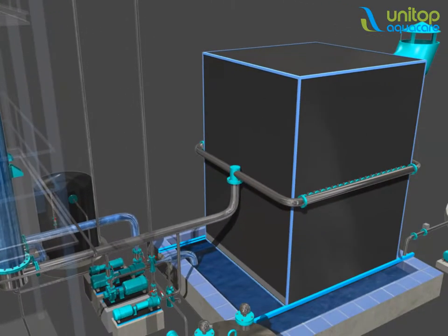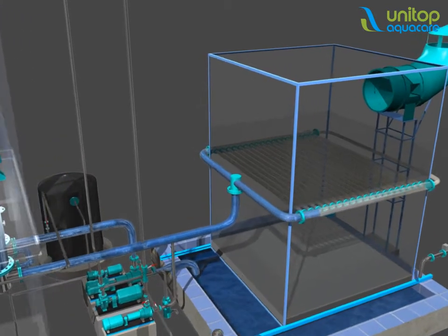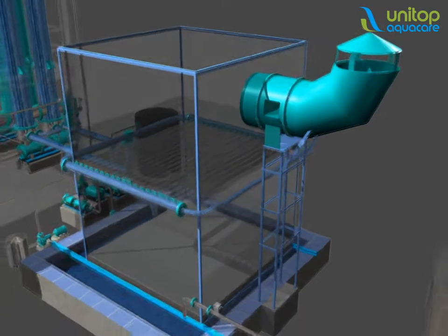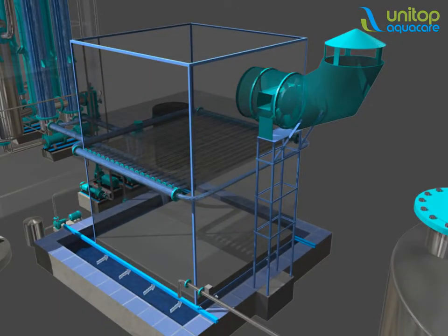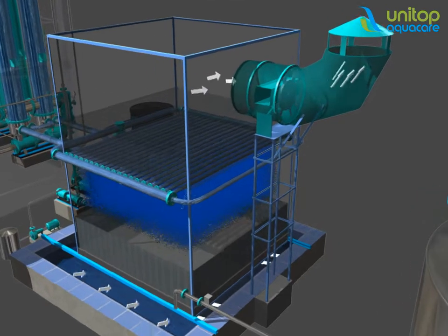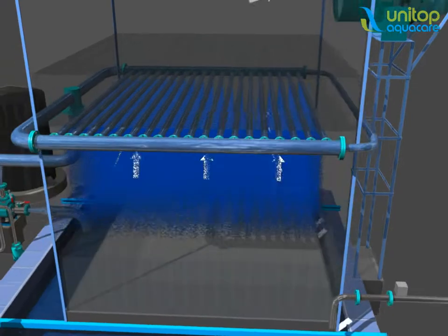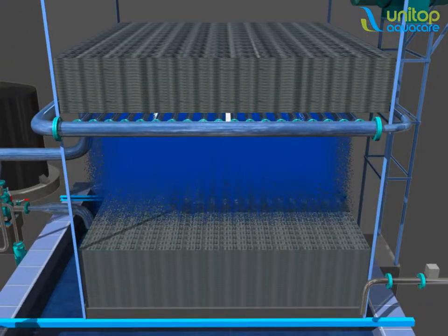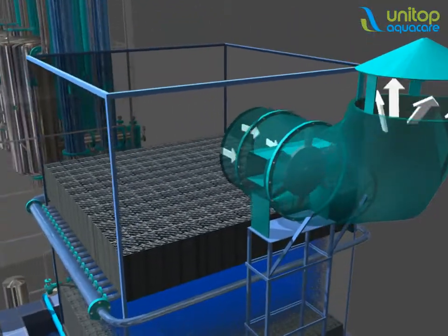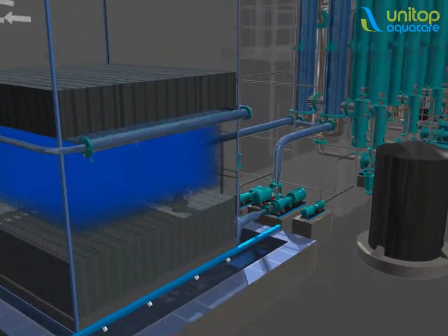During the process, the sensible heat of the liquid is used to evaporate the water in the feed, which comes to you free of cost, saving a lot of steam. The hot liquid is sprayed in the adiabatic evaporator through evaporative fills and gets cooled by the fresh draft of cold air. This method not only saves steam, but also removes the requirement of a cooling tower from the system.